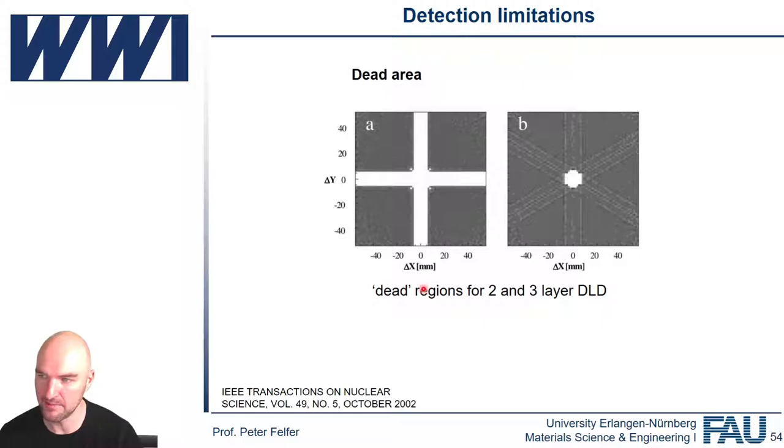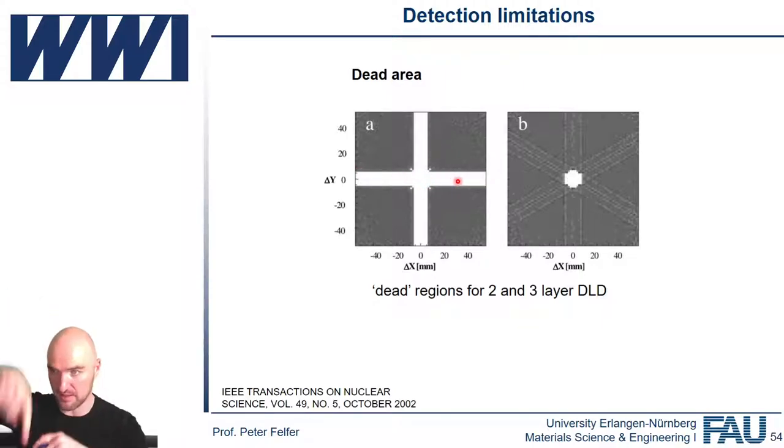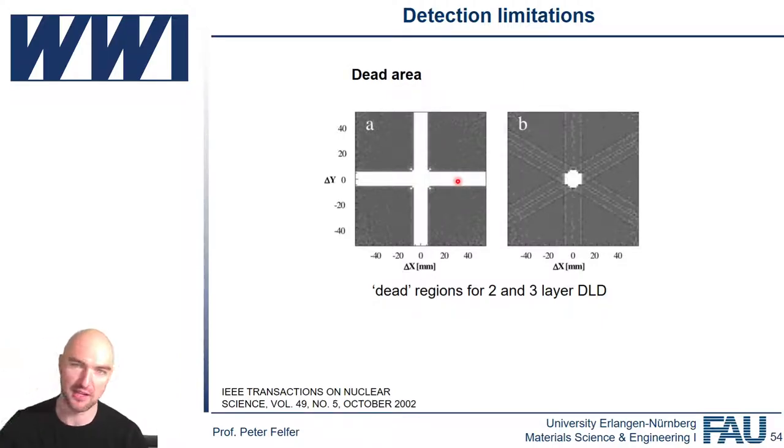So in the LEAP systems, what you have on top of that is a redundant delay line. Because the dead time area has this cross shape, because it's specific to one direction always. And if you have a redundant delay line, you can actually recover anything that's happening here, here, here, and here. This was patented, but the patent ran out last summer. So by now you can freely buy those detectors, and they are offered by RoentDek and by Surface Concept, so you can buy those freely now.